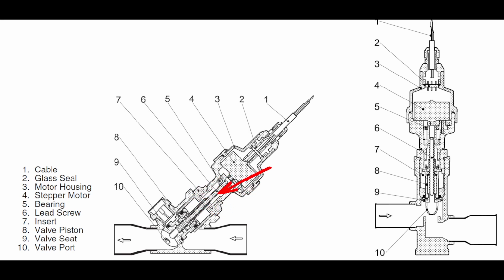If you're sitting there and you're listening and you don't hear this bottom or this top out, it's possible that the valve is sticking via the threads, or it has some bad threads in here and it's not pulling the valve plunger back properly. It didn't make it all the way up to the top. Or even if it did, the threads are so messed up in here that it couldn't put enough force to bind the motor up. And I say bind in a positive way in this particular case. So if we don't hear that top out, that could be evidence of an issue.